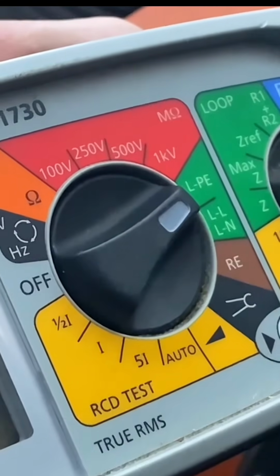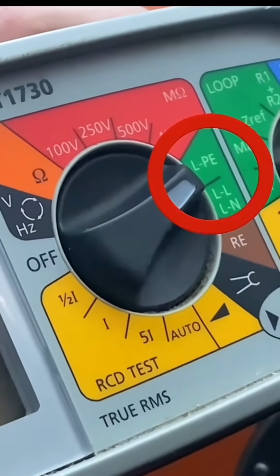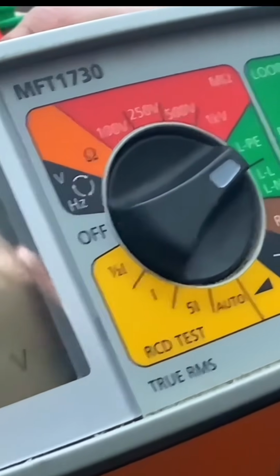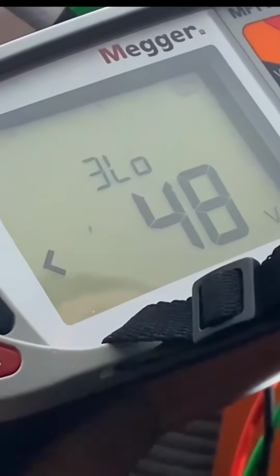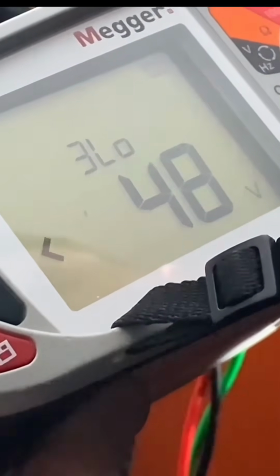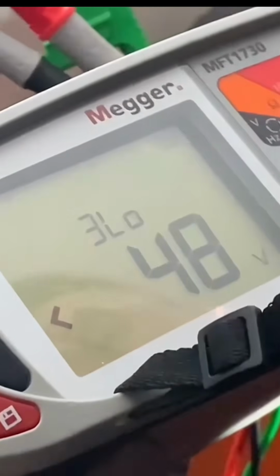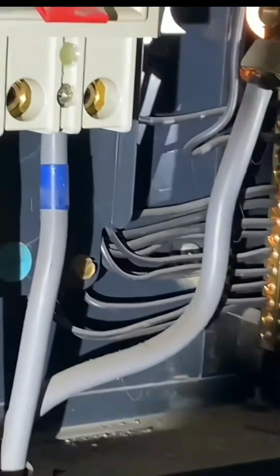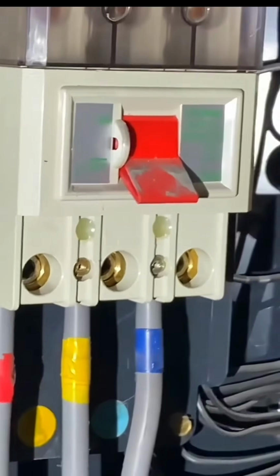So we've set our Megger MFT 1730 up to L-PE, and you're going to do it on the 3-lead low, and that's what you've selected to do it on. We could have done it on high because there's no RCDs, but you think that this will probably be the standard practice to get used to, Matt, is that right, when we've got so many RCDs around, that we go for the low setting? Is that okay? Yes, yeah.